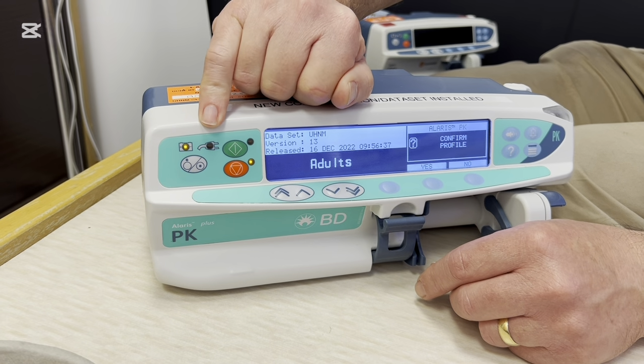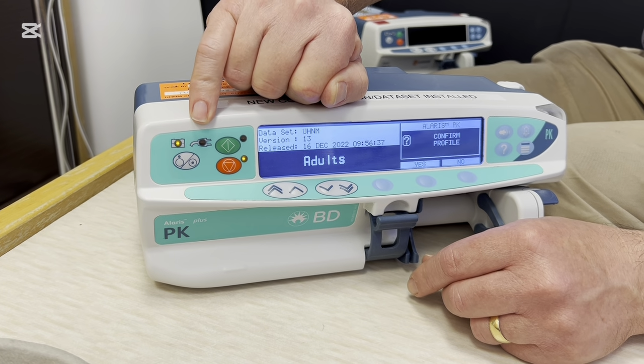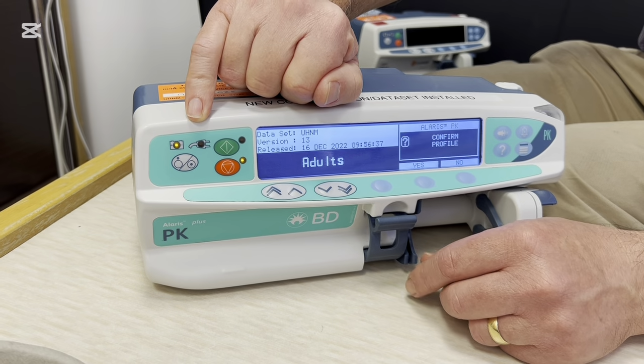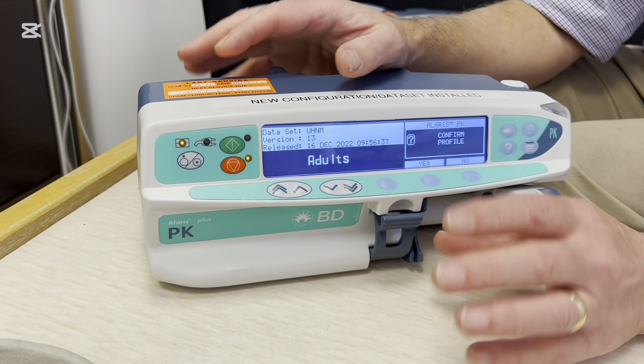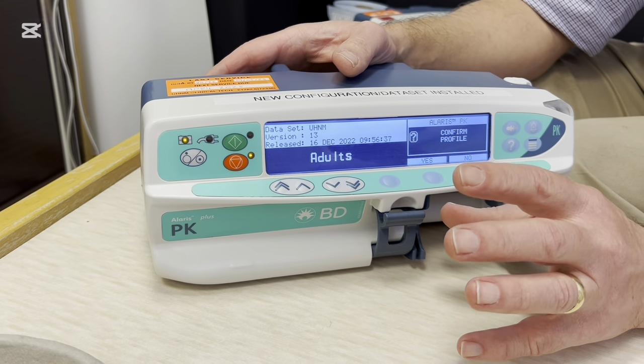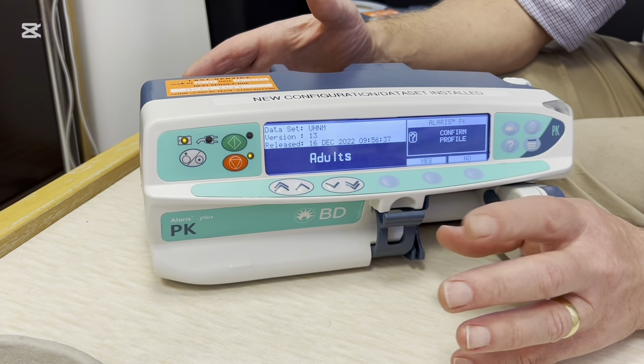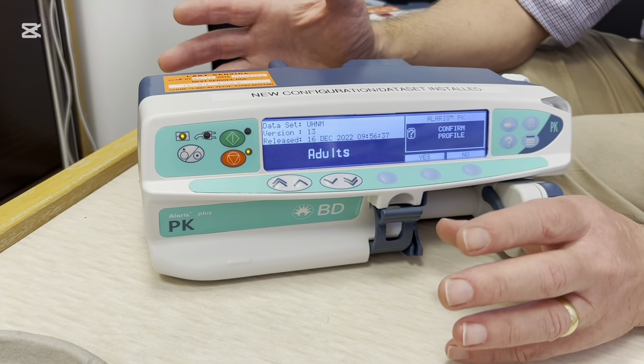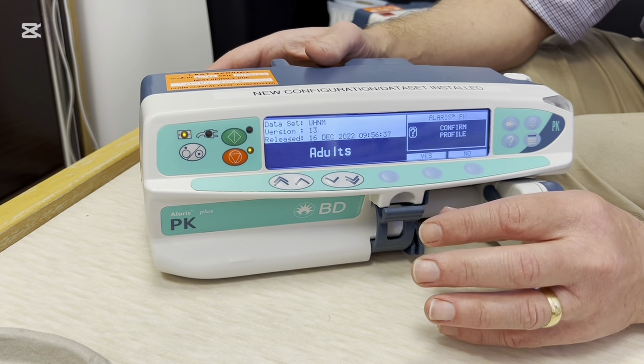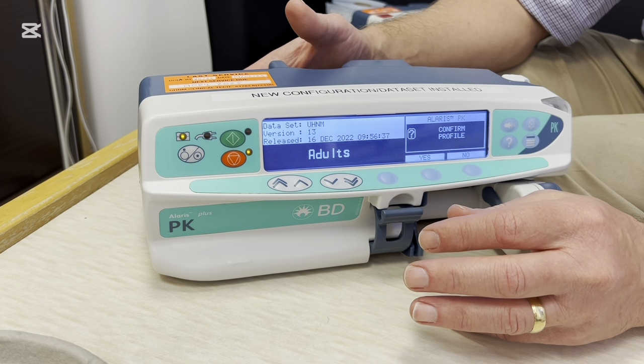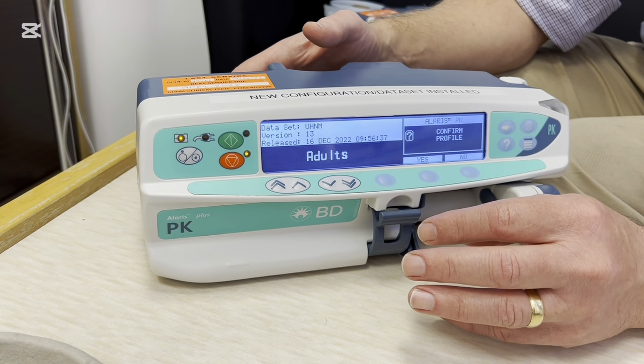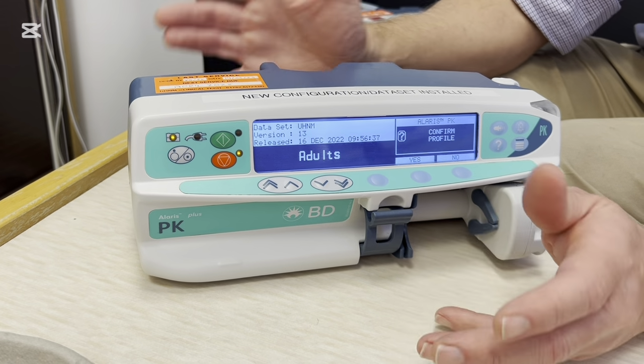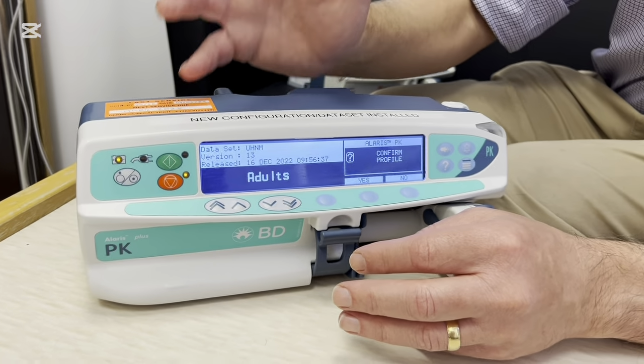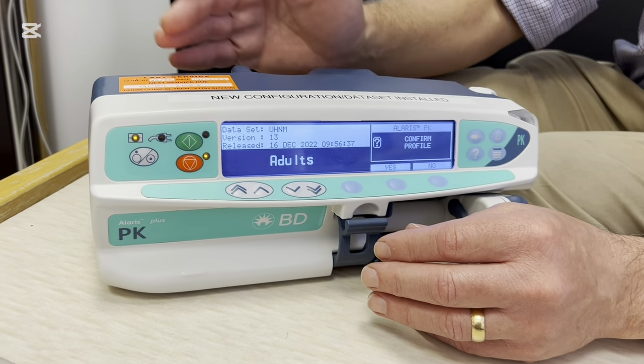We have had instances where people have run it as a battery powered pump, and when the battery fails, if you then plug the pump back in, you'll have lost all the programming data that's in there already. If that happens to you mid-case, it really is a bit of a disaster, and you can't really carry on as a TCI case. It's then very much best guess as to what the infusion rate should be when you swap it over to a different pump. So ideally, as I say, use this as a mains pump with a battery backup.